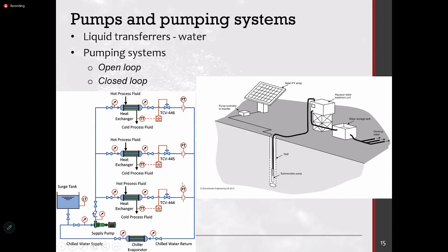And ensure that you are circulating only the chilled water that is absolutely required. So that will save a lot on surface losses and pump flow rate losses. So there are major savings achieved by installing VSDs for this closed loop where you need a variable speed, variable flow rate. So at different times, you need a variable flow rate.